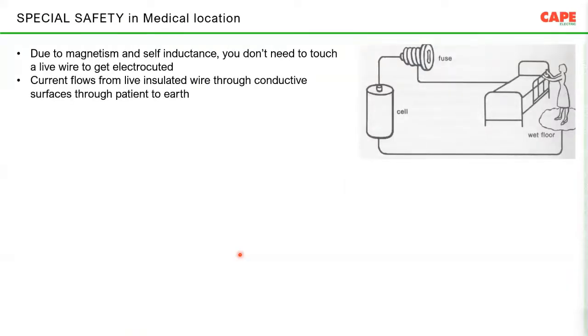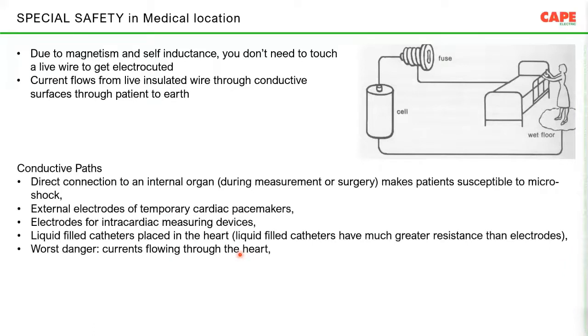So in a medical location, what is the specialty? Due to a lot of electronic biomedical equipment using magnetizing or self-inductance for normal operation, sometimes you don't need to touch an equipment to get a shock. Current flowing through the insulation itself sometimes creates some kind of shock hazard. And a lot of conductive parts exist, and probably they are also connected to the human, like direct connection to an internal organ during measurement or a surgery.